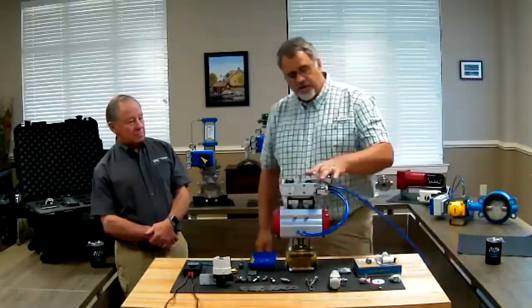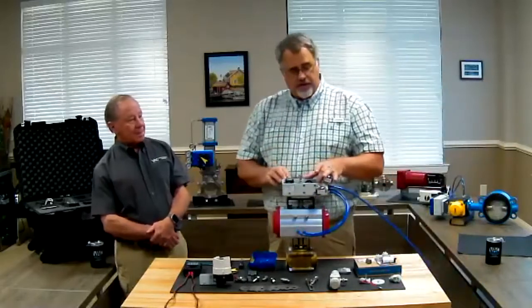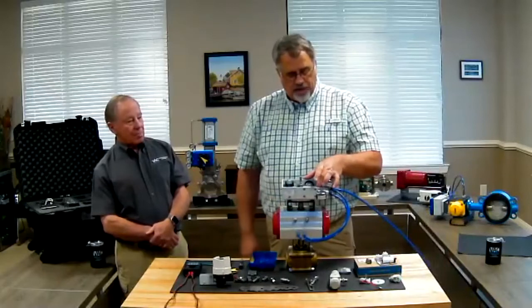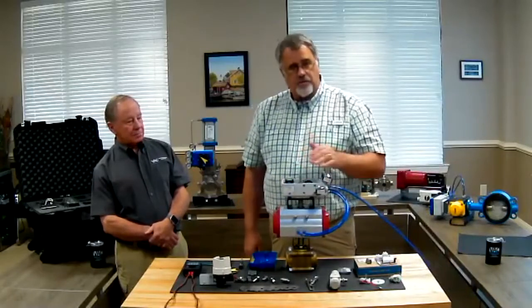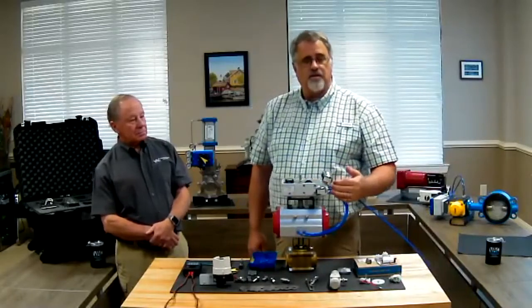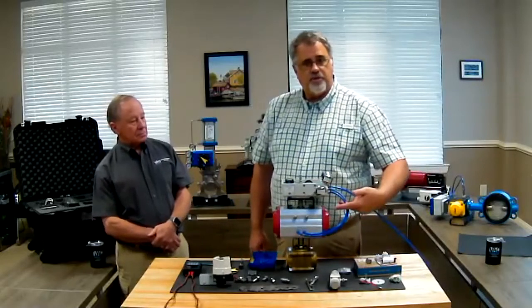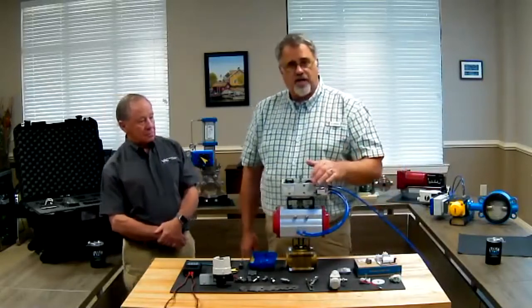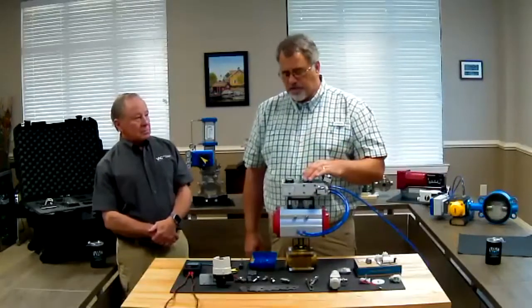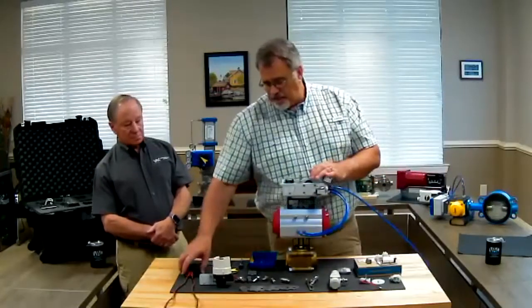So I can do that by just reaching in, and there's a balance arm in here. And again, there are YouTube videos that show this in detail, but I can pull out and just confirm that the actuator's turning in the correct direction. If it did not turn, chances are I just need to flip these two pieces of tubing. You're teaching the customer how to troubleshoot just by showing them these things as you go. So I've confirmed that mechanically it's correct.